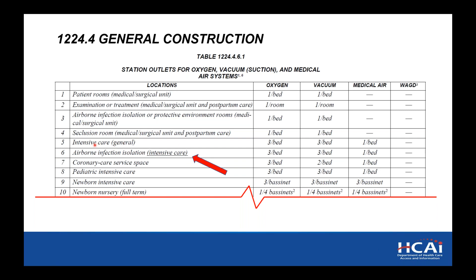And then under the nurse call devices, it's always been a misconception that a toilet in an OSHPD 3 clinic required a call station for nurse call. Electrical code referred back to this table that said patient toilet room for 1226 had a dot there, says you need a call station for a toilet room in a clinic. If you actually go to the text for 1226, it never gets you there. So it's never been required, but it's often been added for no reason at all. So we're adding a subnote number 1. It says not required for primary care, chronic dialysis, rehab, or psychology clinics. So hopefully that'll end a lot of that confusion.